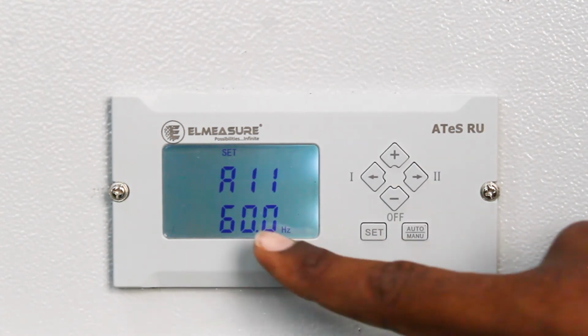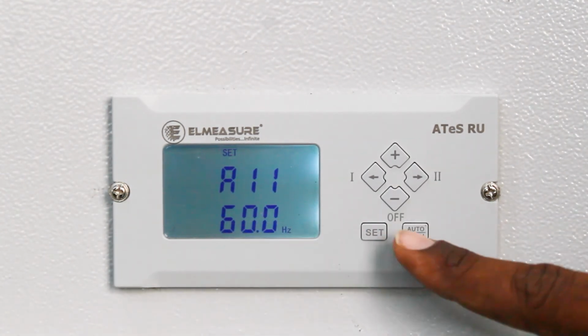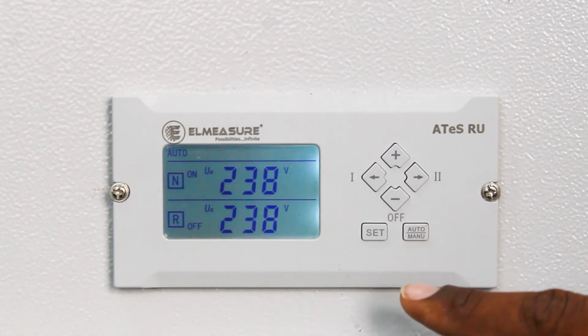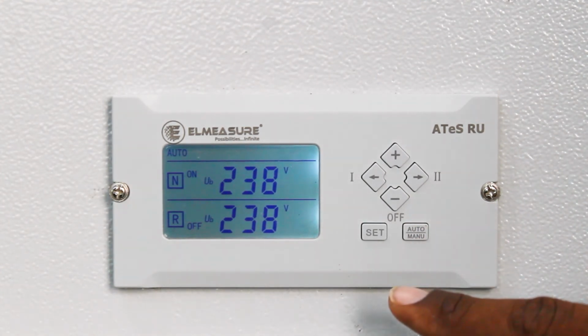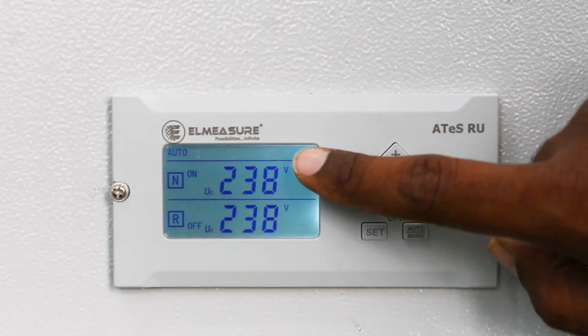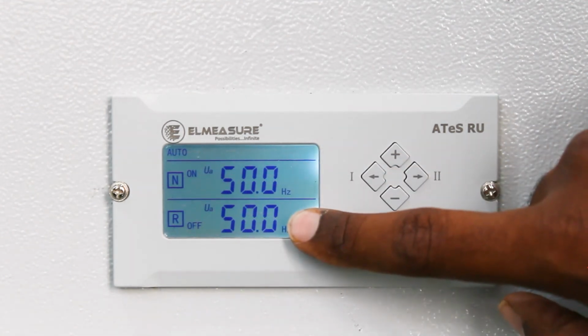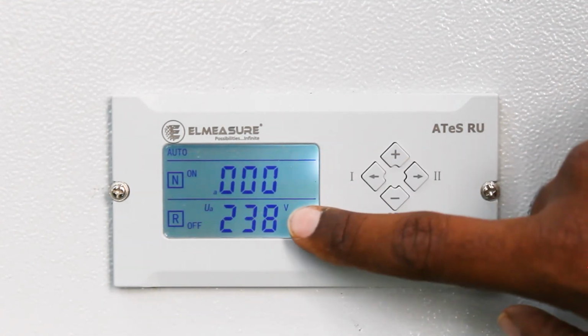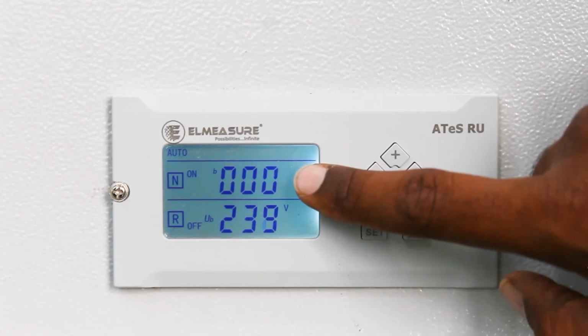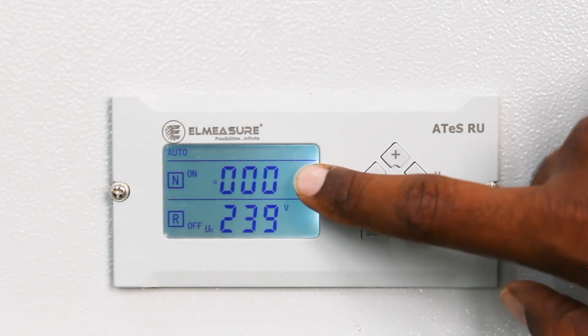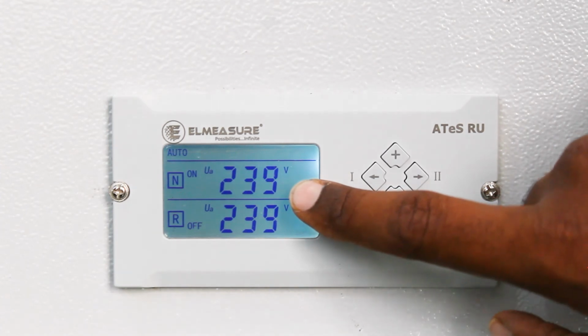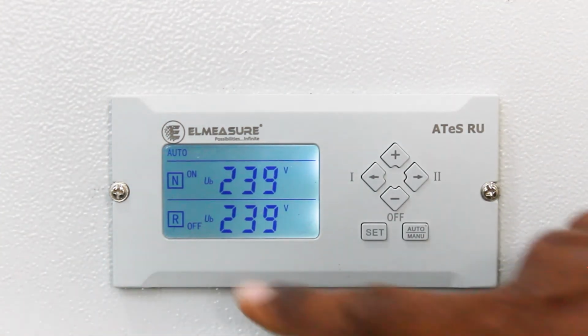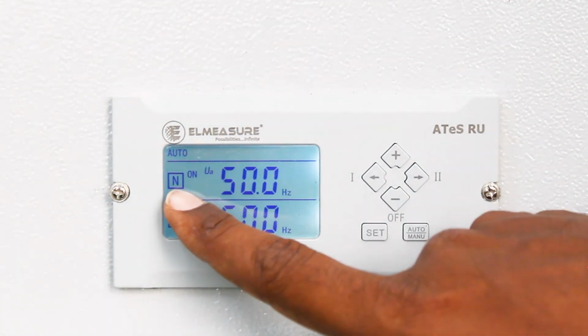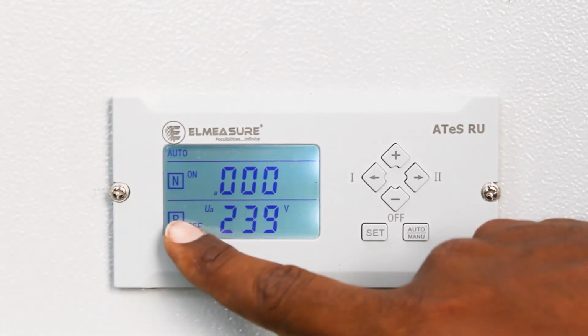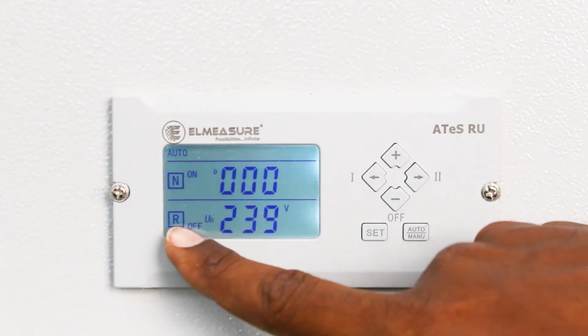Once the program is done, press the auto button and the program will save automatically. Also you can see here we can monitor source one as well as source 2 three-phase line to neutral voltage and frequency. N means normal source one, and R means reserve source 2. So source 1 is on and source 2 is off.